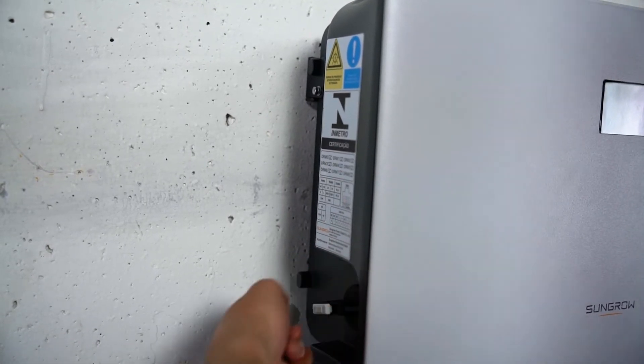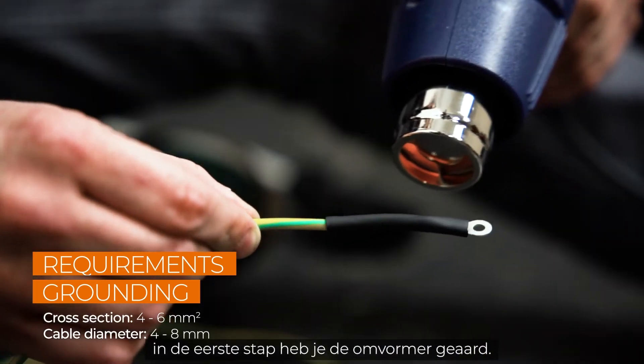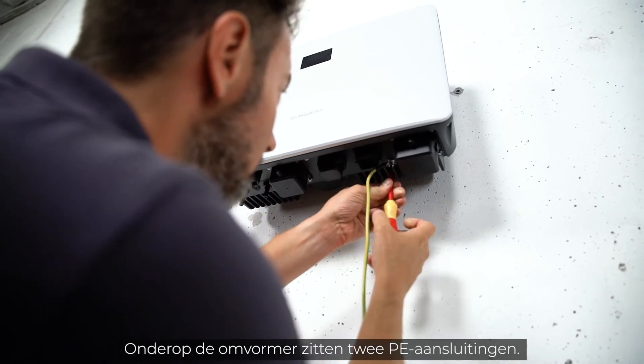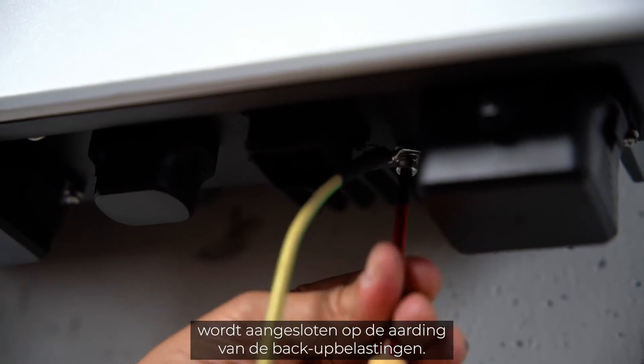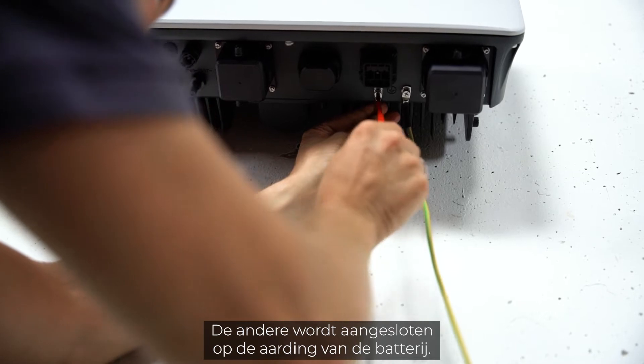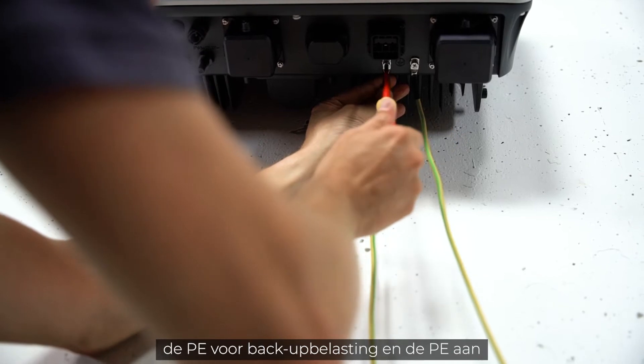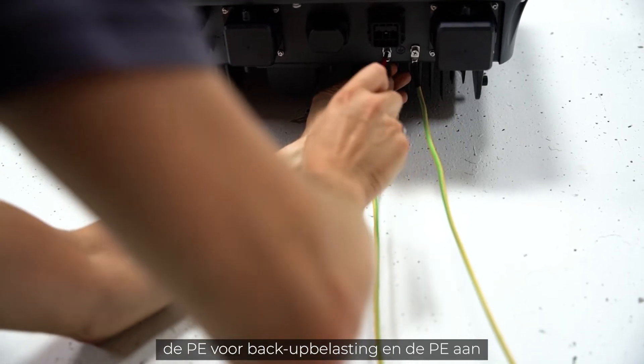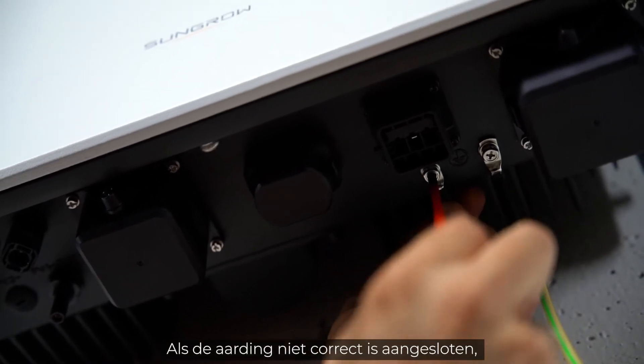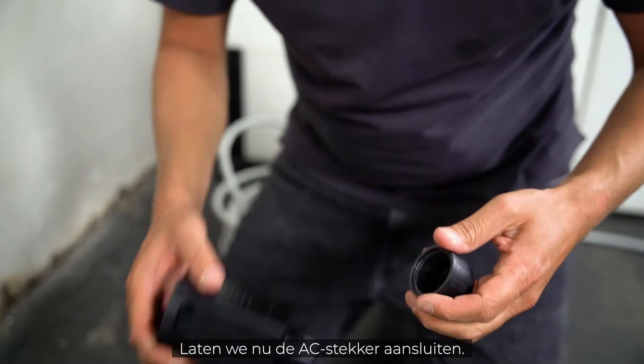Now let's continue with the installation. In the first step you have to connect the inverter to ground. There are two PE connections at the bottom of the inverter. The one below the backup port will be connected to the grounding of the backup loads; the other one will be connected to the grounding of the grid. Make sure that the chassis of the inverter, the backup load PE, and the grid side PE are all connected to the same grounding point. If the grounding connection isn't done properly, it may affect the backup function.